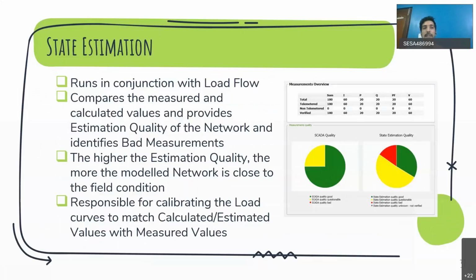So we are getting measured data from substations and different RMUs. Apart from that, load flow is also calculating the same data based on all the known values. So what state estimation does is compare the measured data with the calculated data and match them. This is done to identify any bad measurements, something wrong on the measuring side or something wrong on the networking side.